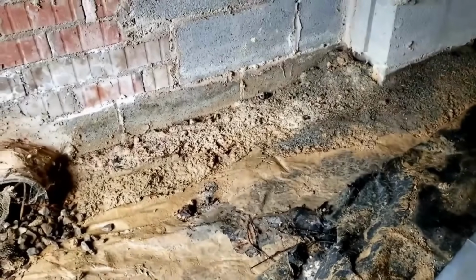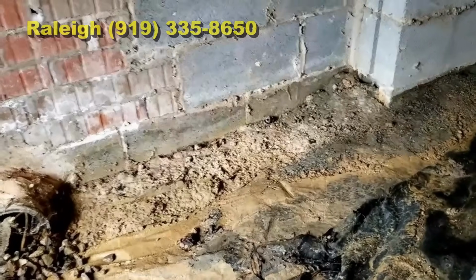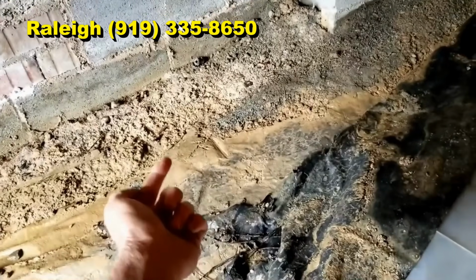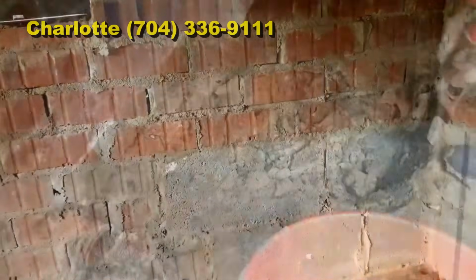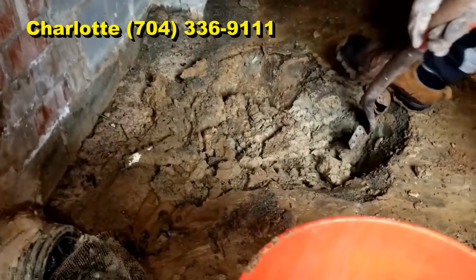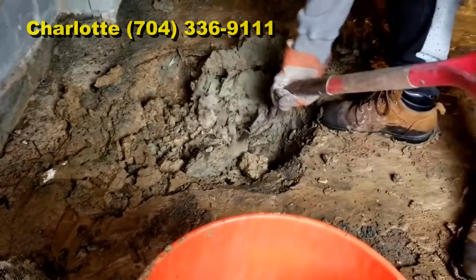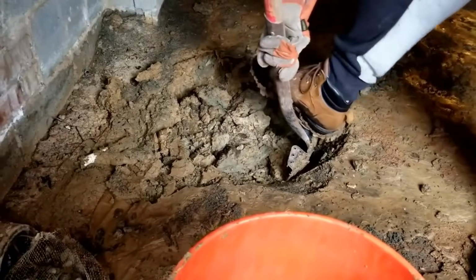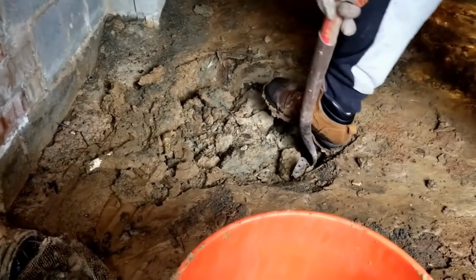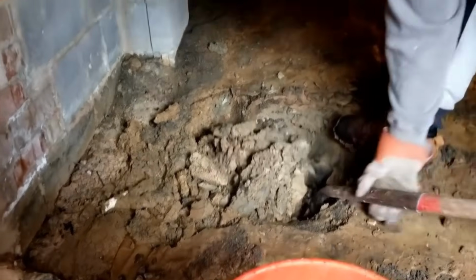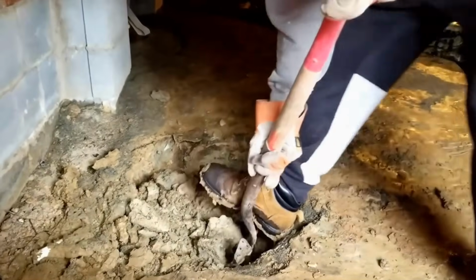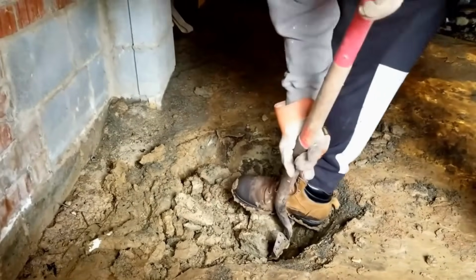But right here in this corner, we're going to go ahead and sink a sump basin, put a Zoeller M53 down in the basin, pump it up through a riser, and we're going to drill right through that wall and send it right outside. So to get started, what you need to do is get a small shovel. This is just a full-size shovel. We have lots of different sizes. We're going to go ahead and dig a round hole down about 2 feet. And this is clay, but we've got good headroom, as you can see, so you're able to actually stay bent over. This only takes maybe 15-20 minutes.